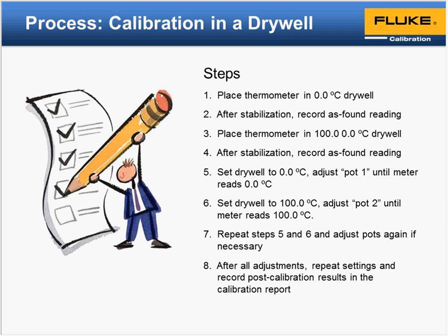Once we've done that, now we go back to the 0 point. So again, we've now recorded our as-found, or what we are currently at, and go to 0. As the trim, as an example, we adjust until we see 0, and then we'll move to the second set point of 100C and adjust that pot as well. Same thing here on that linear slope. If you're not seeing what you want, or you're adjusting one and then you go back and it pulls the other one out, sometimes you do have to split that difference on slope.